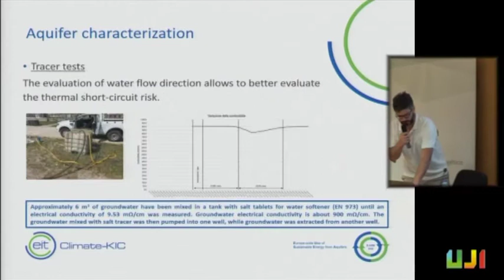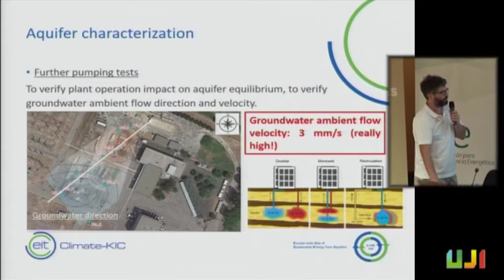We also made a tracer test to see if there is a risk of what is called thermal short circuit. So if we extract here and pump the water here, there's the possibility that the water pumped here gets taken back by the pumps. We create a sort of circuit that is not good, because if we cool down the water and pump it, then we end up using already-cooled water. So the efficiency of the system goes down in wintertime, and obviously the opposite can occur in summertime.